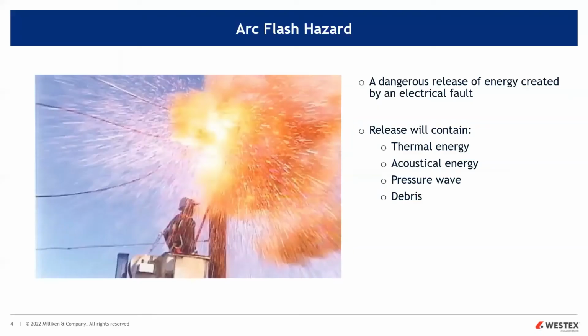So I'm going to go through this fast because I know a lot of people here are well versed on arc flash, but just the basics here. Of course, it's a dangerous release of energy, it's electrons and air, if you will. It will release radiant and thermal energy. They're very loud. Hearing protection is required in 70E. And when you superheat air, you get a pressure wave. So with the arc flash, you get the blast. Then there's a lot of debris. These arc flash events are truly molten metal events. You've got a lot of molten copper coming out on older equipment, molten aluminum if it's newer equipment. So that molten metal can also be a risk factor. Not only can the radiant and thermal energy coming off the arc ignite regular workwear, but the molten metal can also be a culprit in igniting workwear.